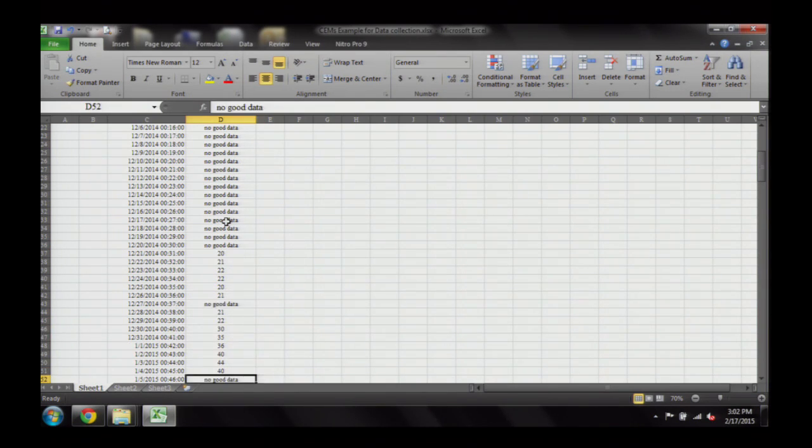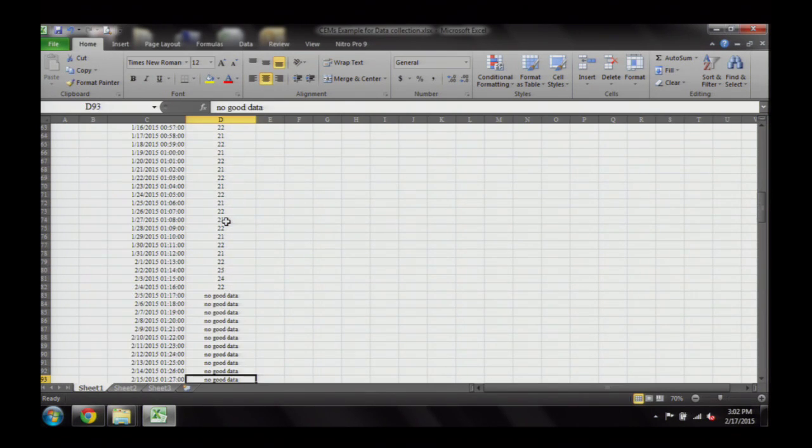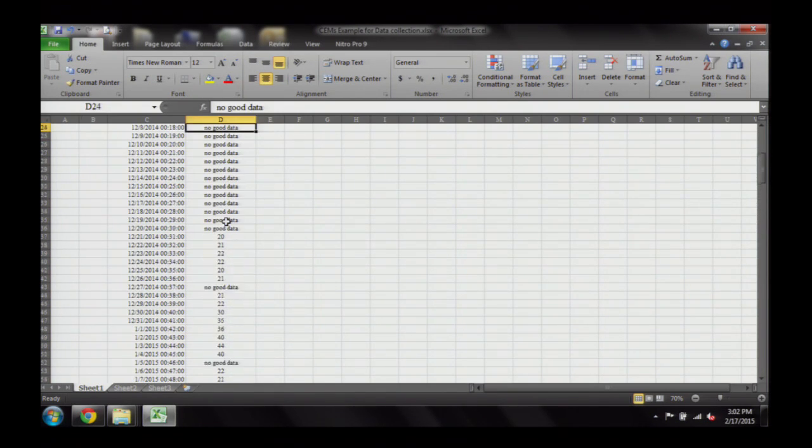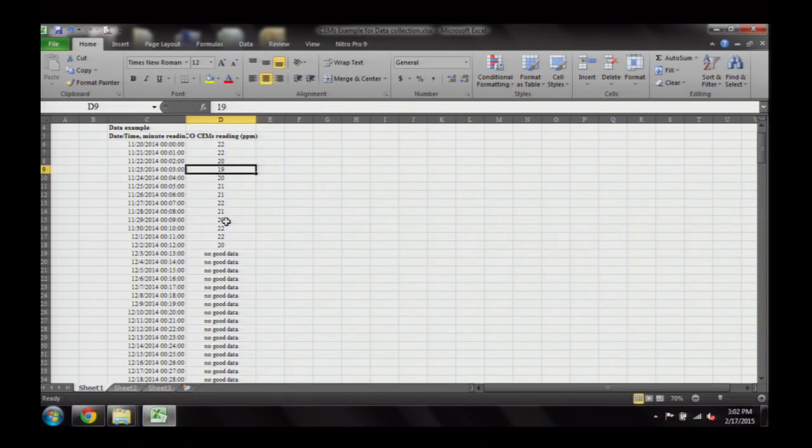Okay, so then I moved down here further, and I still have a few where I'm throwing out data. So how do you say that you had a data point from that quadrant? That would not be a valid hourly average under Part 75. Yeah, I'm in Part 60. I live in Part 60. But from 15 to 30, you have no good data, and that's one full quadrant. Oh, you're right. Because it starts at 31, not 30. But from 15 to 30, I didn't get anything. So you're right. Thank you.